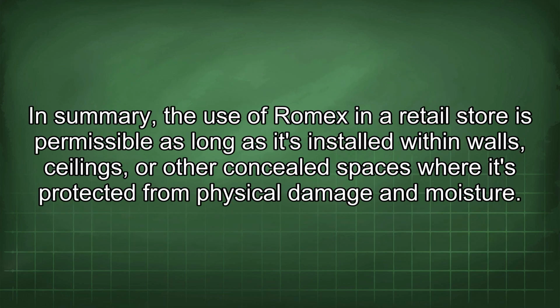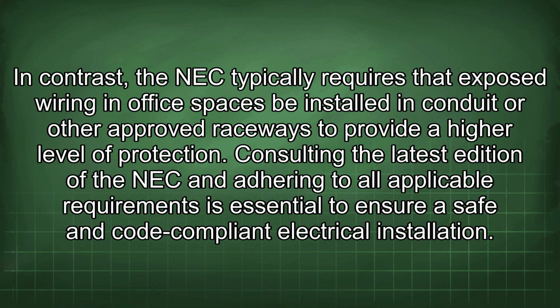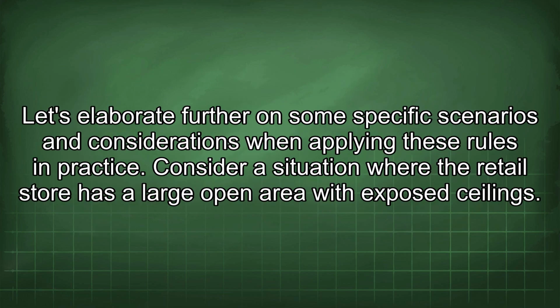In summary, the use of Romex in a retail store is permissible as long as it's installed within walls, ceilings, or other concealed spaces where it's protected from physical damage and moisture. In contrast, the NEC typically requires that exposed wiring in office spaces be installed in conduit or other approved raceways to provide a higher level of protection. Consulting the latest edition of the NEC and adhering to all applicable requirements is essential to ensure a safe and code-compliant electrical installation. Let's elaborate further on some specific scenarios and considerations when applying these rules in practice.